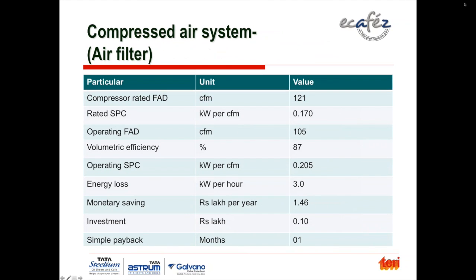Now this is moving on to the example of energy saving by changing the air filter. Particularly in this example, usually air cleaning of the filter is sufficient, but here the filter was worn out, so it actually had to be replaced. The typical rating of the compressor is given as 121 CFM. Now, what was the rated CFM? The rated specific energy consumption of the air compressor was 0.17 kilowatts of energy per CFM.